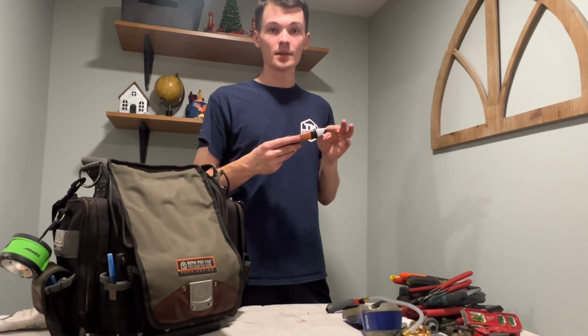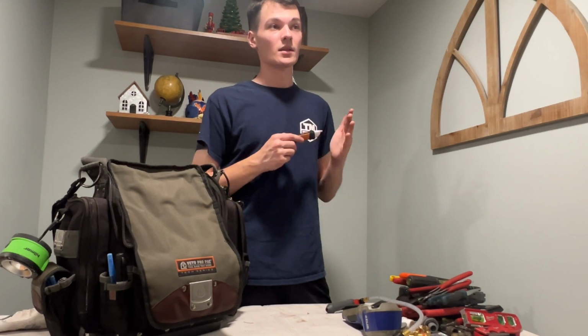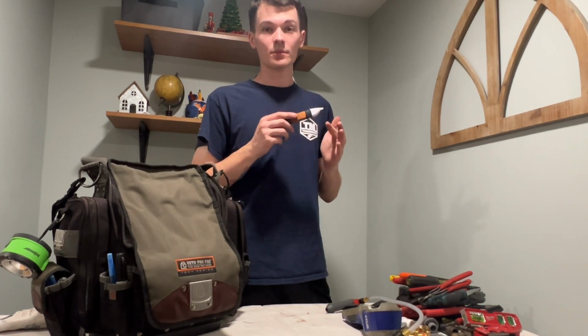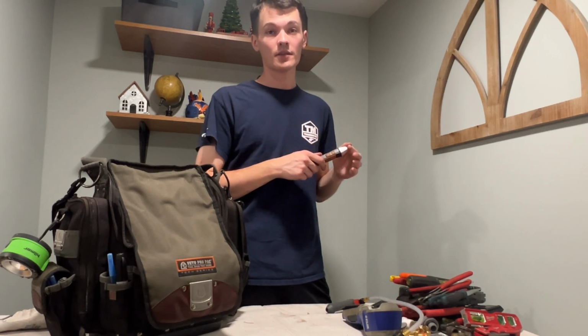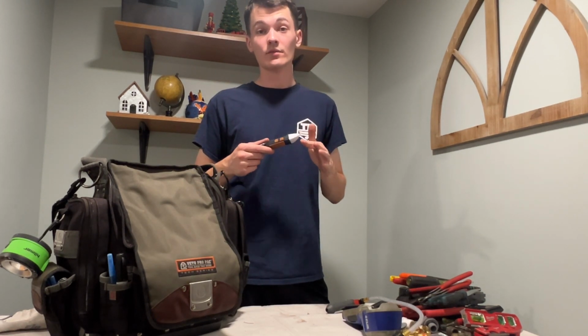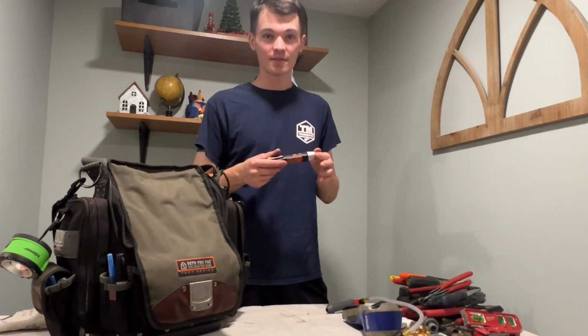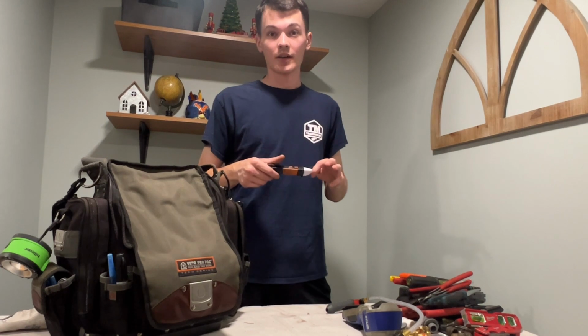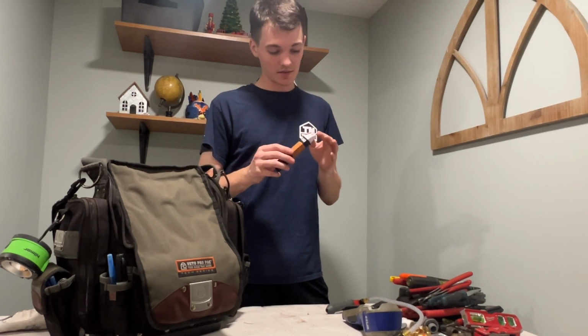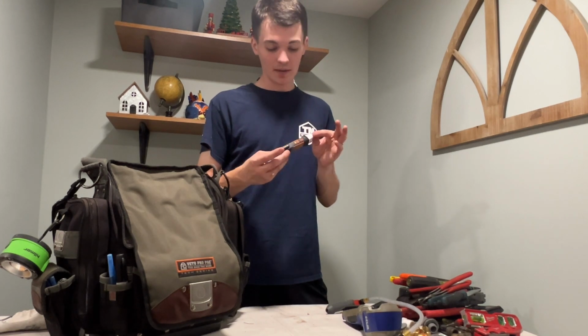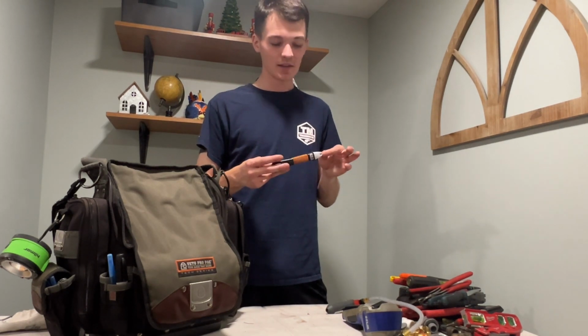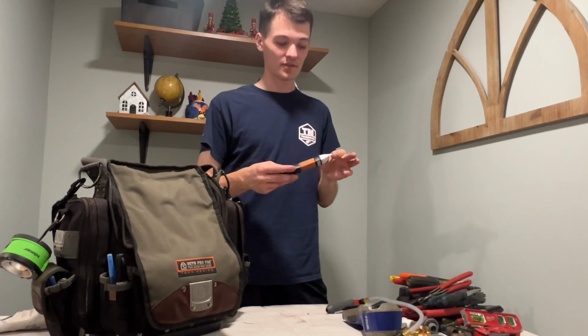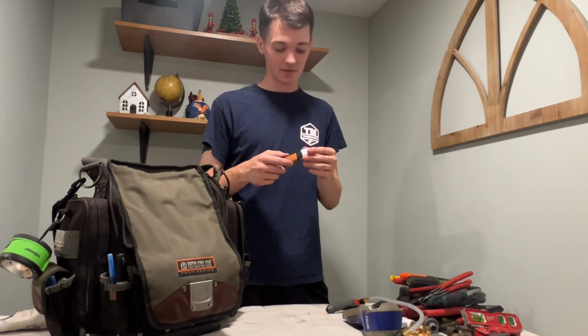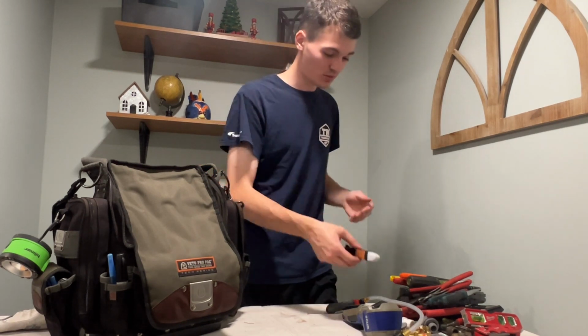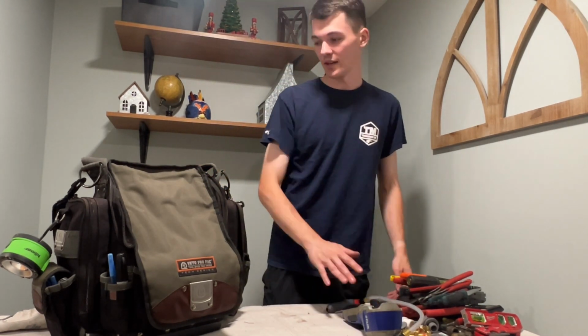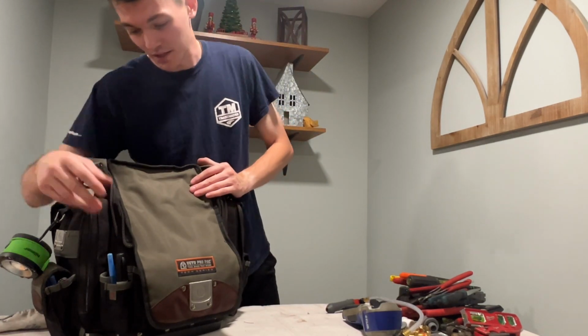The other day I was testing wires for a blower motor, and it was reading voltage on the 24-volt wires, but not on the line voltage wires, the ones that would kill me, when I knew there was power there and confirmed it with a voltmeter. So I don't trust this anymore. I'm a little hesitant to use any non-contact voltmeter now, because that's a serious flaw, not reading the line voltage, the 240 volts, but picking up the low voltage control wiring. So I wouldn't recommend that tool, but right now it's in there.